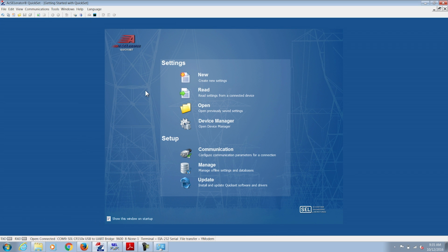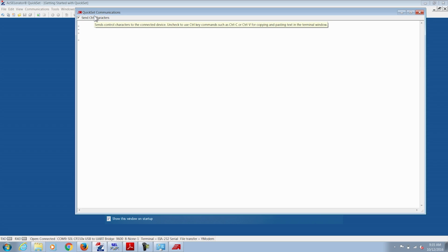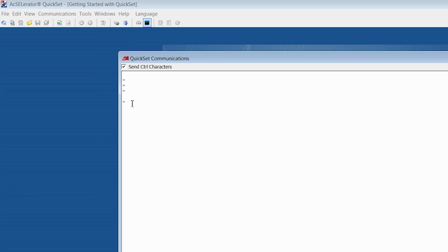and OK. So now to verify if we've established communication to the device, go to the terminal, which is that terminal icon right here. You open it up, and when you have it open, you hit enter. If the relay responds back to you with an equal sign, that is the sign that you have established communication with the SEL relay. Now there are different access levels, as I mentioned.